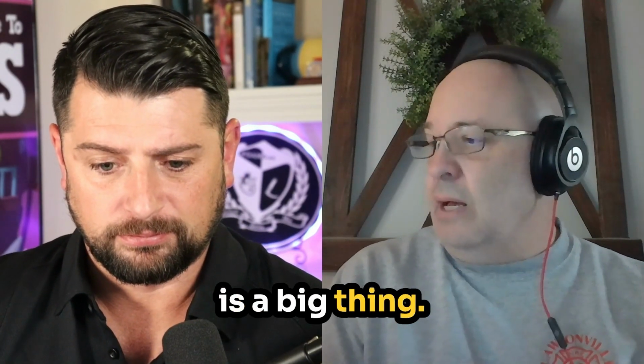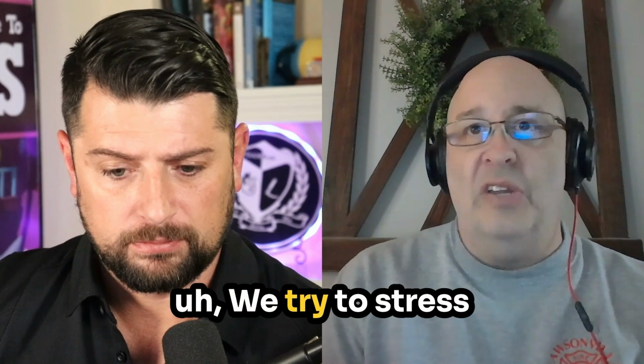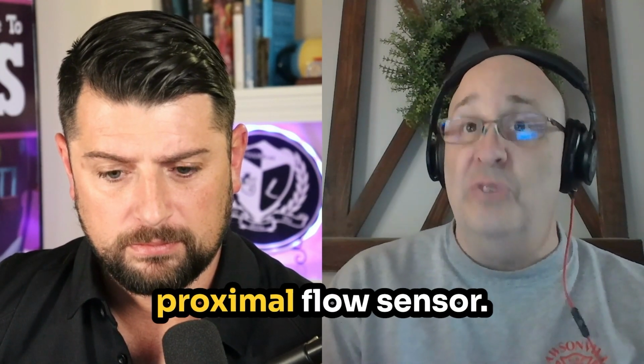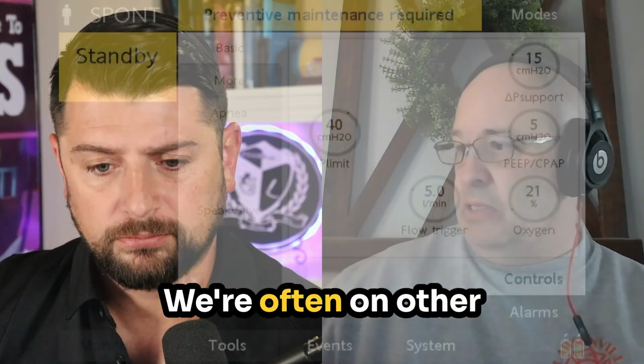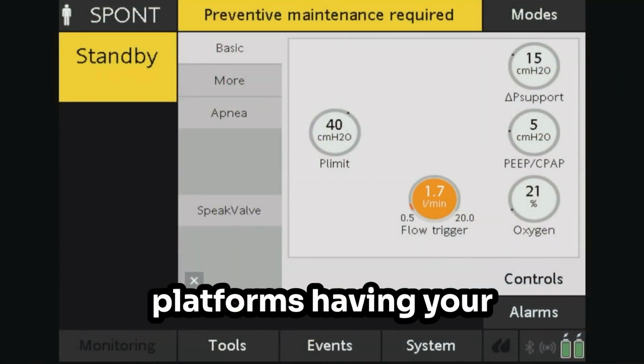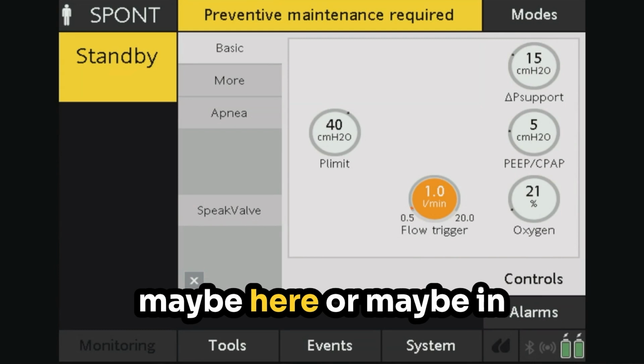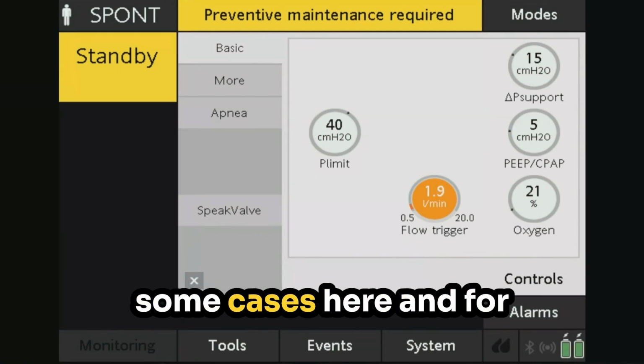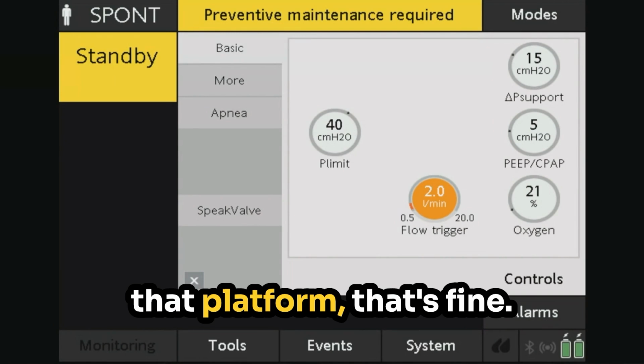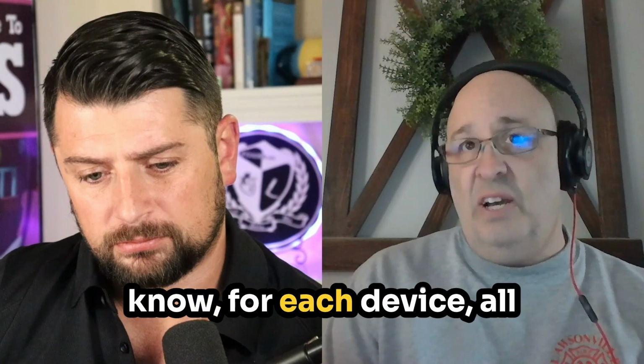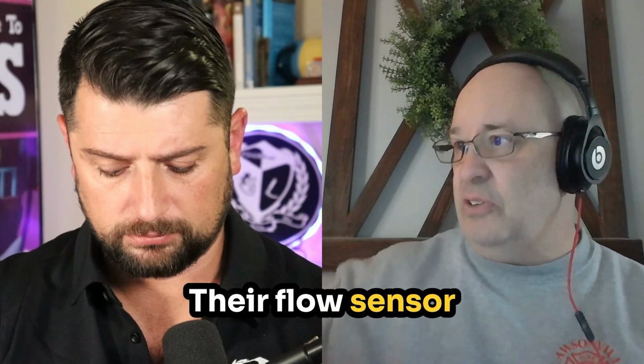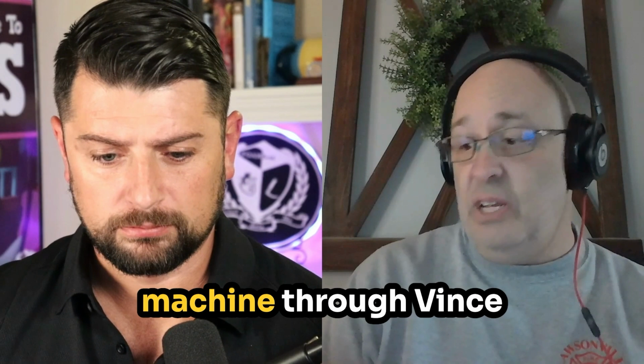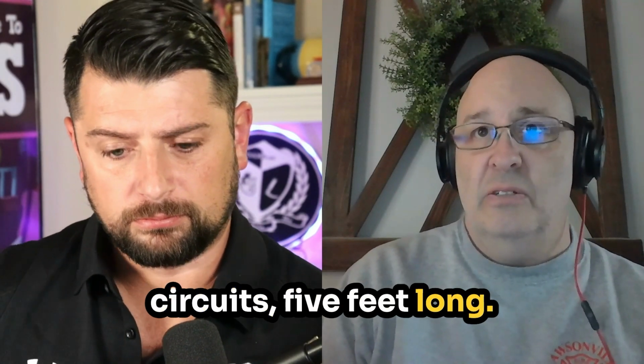So flow trigger is a big thing. This is one of the biggest things that we try to stress coming to the Hamilton platform with the proximal flow sensor. We're often on other platforms having your sensitivity or flow trigger maybe here, or maybe in some cases here. And for that platform, that's fine. The big question is, for each device, all machines are different. They have some similarities. They have differences. Most machines have their flow sensor back inside the box. So if the Hamilton were that way, or any machine, your vent circuit's 5 feet long.